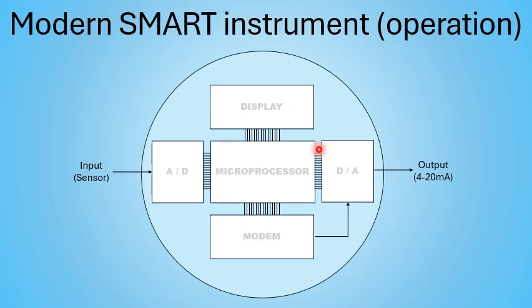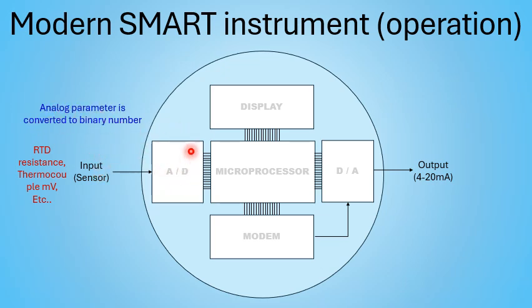So there's a lot going on in this instrument. Let's start at the beginning. Basically, the parameter, whatever it is, RTD resistance, a thermocouple's millivoltage, etc., comes in. That analog parameter is converted to a binary number. You can see there's a big binary number. That binary number represents something to the microprocessor. It's essentially scaled in a digital numbering scheme.